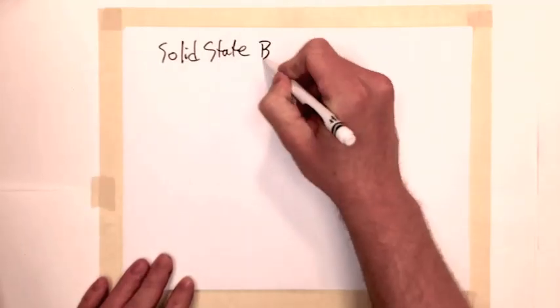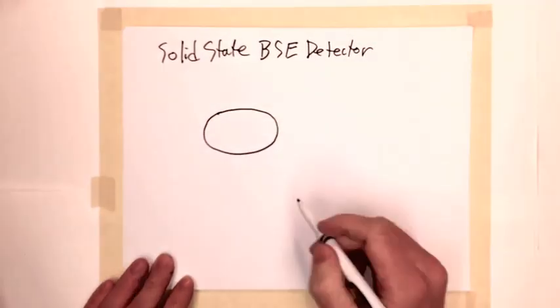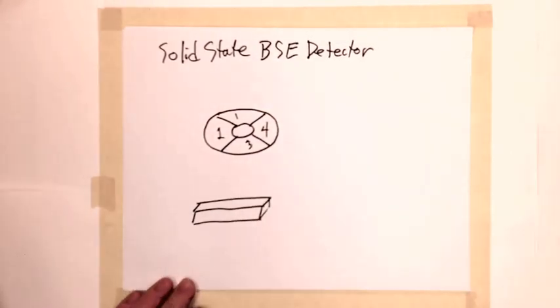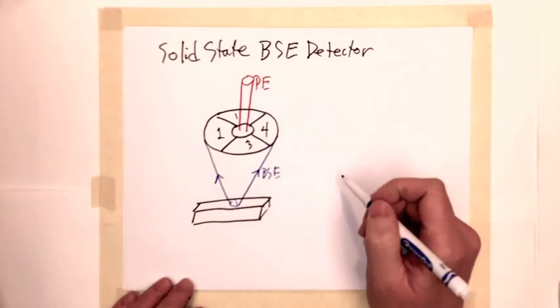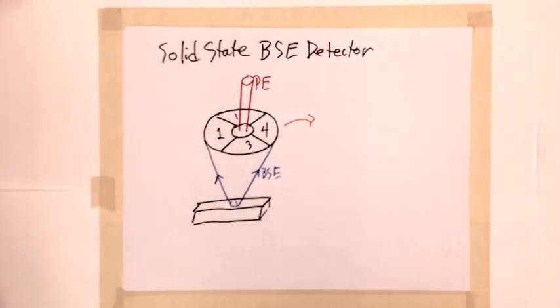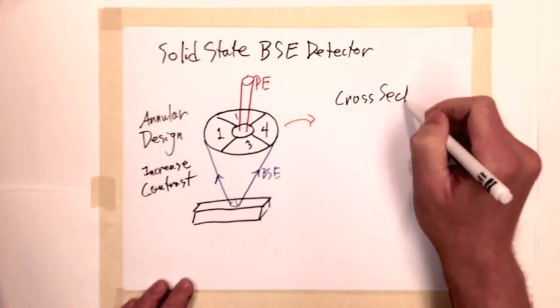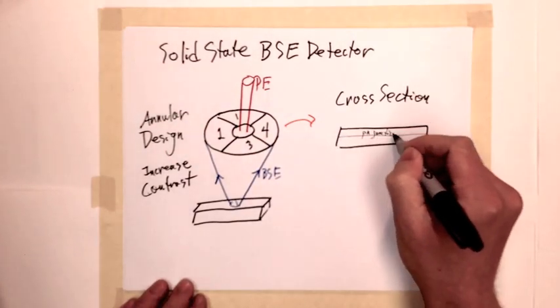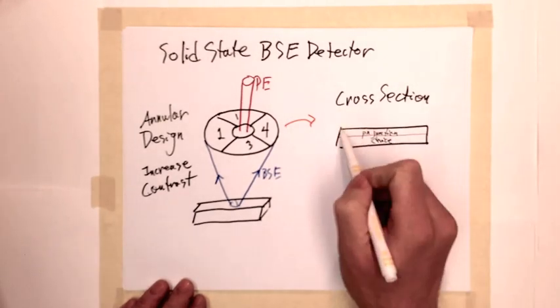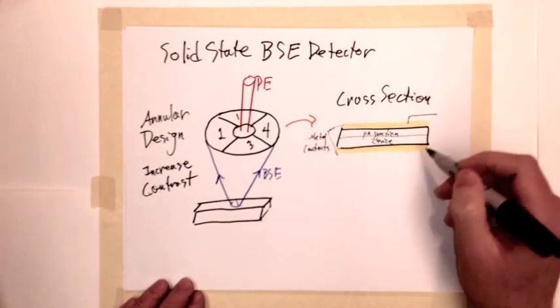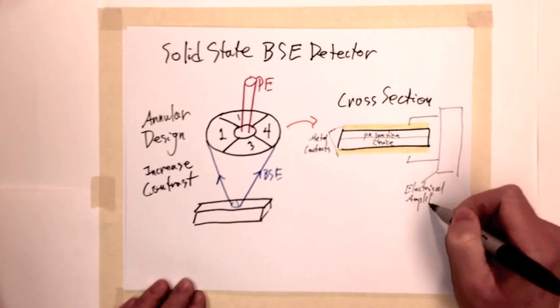Dedicated solid state detectors are one of the primary ways of detecting backscattered electrons. A biased p-n junction is made in an annular configuration just under the final lens aperture. Electrons landing on the detector will generate current that can be measured with an amplifier circuit. If the annular detector is divided into quadrants, the signal from the individual quadrants can be added to produce increasing atomic number contrast or subtracted to produce stronger topological contrast.